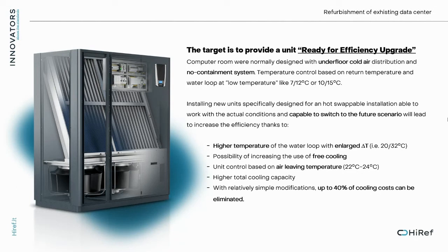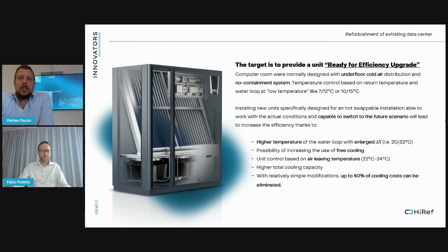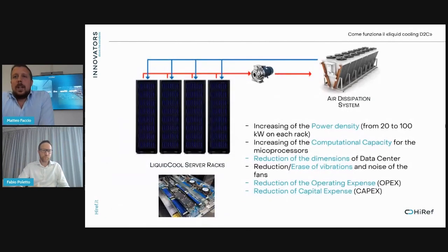When all the units have been substituted with the new ones, these units are capable of switching to the future scenario, so they are able to work with a higher water temperature, for example 20/32, giving the possibility to increase the free cooling capability of the system. The unit is designed to control the supply air temperature and not the return air temperature anymore, and with this simple modification, we can achieve up to 40% saving of the cost of cooling distribution and production.